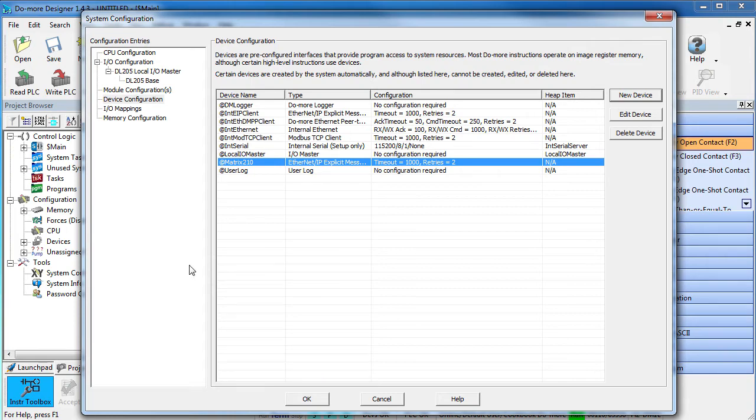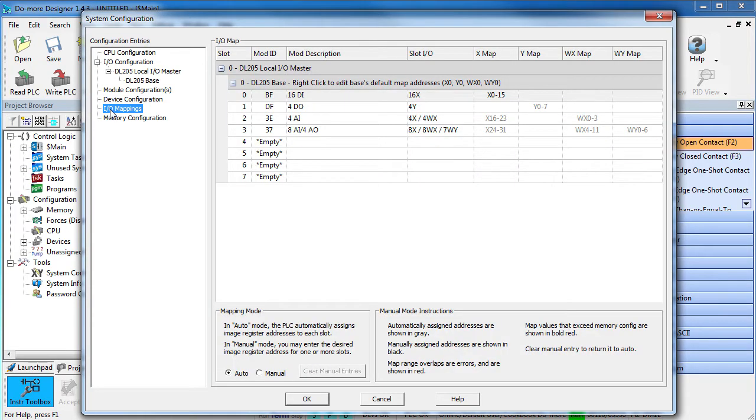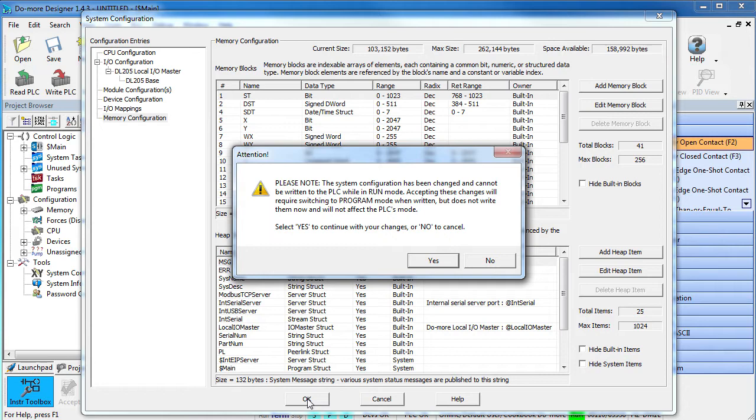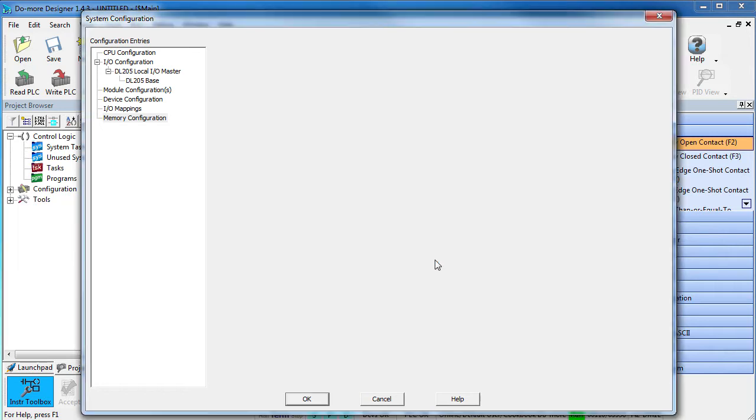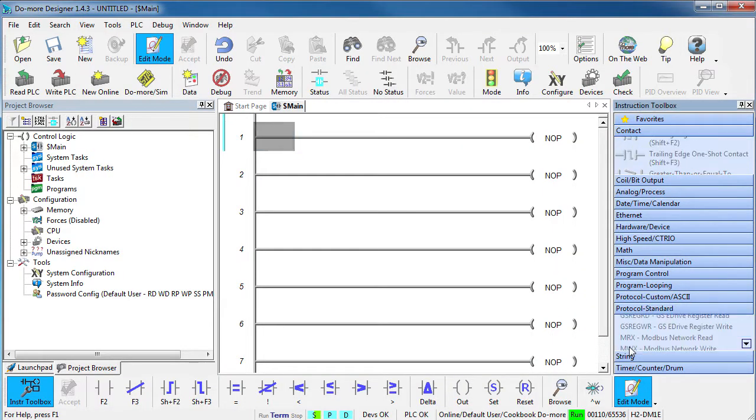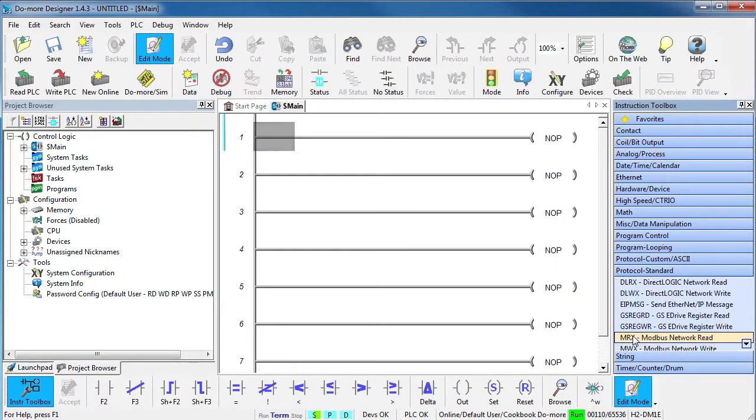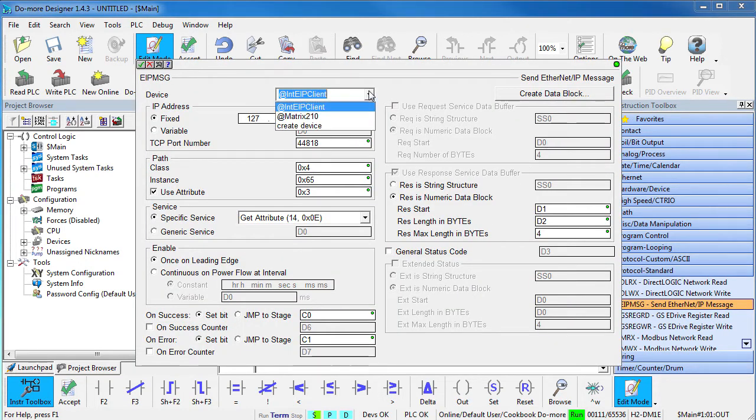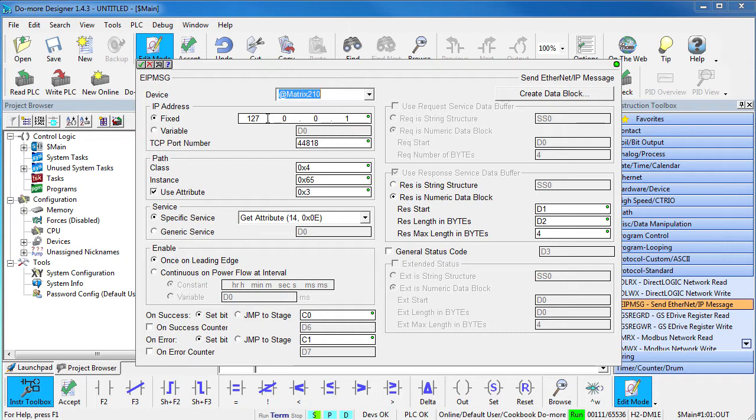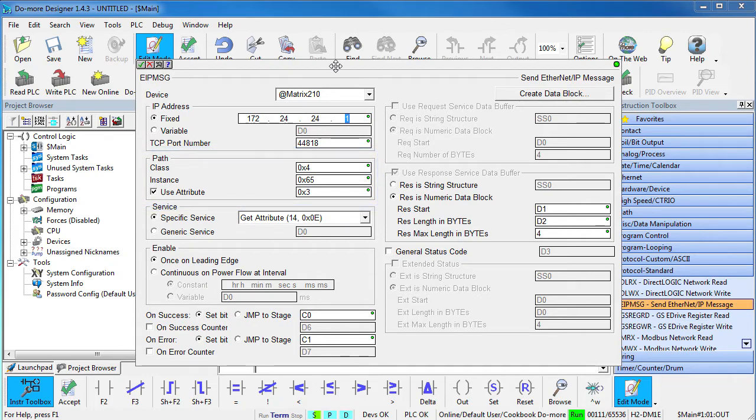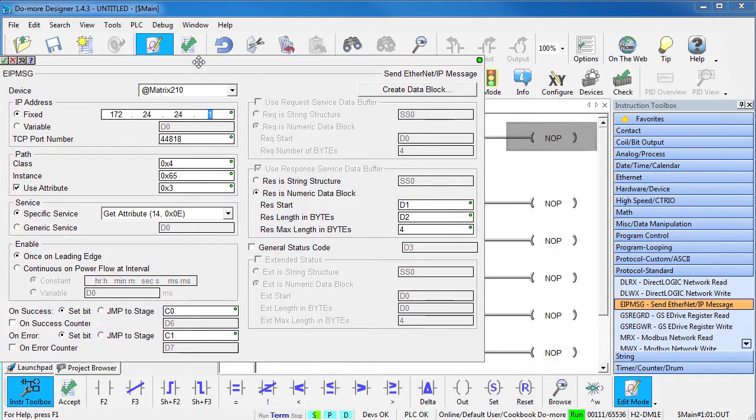We don't have any new I/O and the Ethernet IP device we created doesn't use any heap structures for us to talk to so we're done configuring the Do-more and we're ready to talk to the Matrix 210 imager. To do that, we just grab an Ethernet IP instruction, drop it on a rung and fill in the blanks. We want to use our new Matrix 210 device and he's at this IP address. This is where we put the codes we use to talk to the Ethernet IP device. Where do you get the codes?